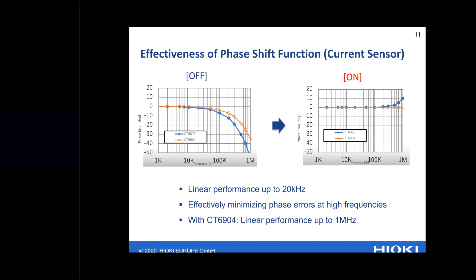But what you want to achieve is a more constant and more accurate measurement result across the bandwidth. And that is one of the reasons why, when you turn on that phase shift correction function in combination with the current sensors, where the power analyzers know the characteristics across the frequency bandwidth, you will be able to increase the performance of the measurement result up to 1 megahertz. And at the end of the day, that will then give you a better understanding of your power system.